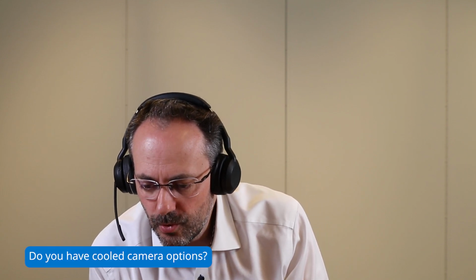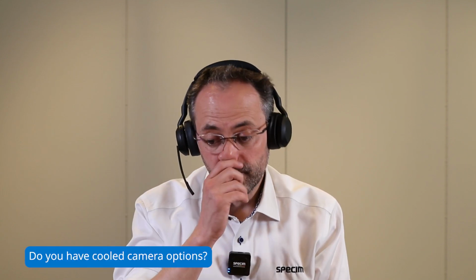Do you have cooled camera options? Yes, we do. But the FX10 is not cooled. The FX17 is stabilized, but the SWIR camera between 1000 and 2500 nanometers is cooled. The FX50 between 2.7 and 5.39 micrometers is also cooled, as well as the FX120 between 7.7 and 12.3 micrometers. So three cameras, basically, are based on MCT sensors, and in order to be sensitive with a good SNR, you need to cool them at the cryogenic level with a Stirling pump.